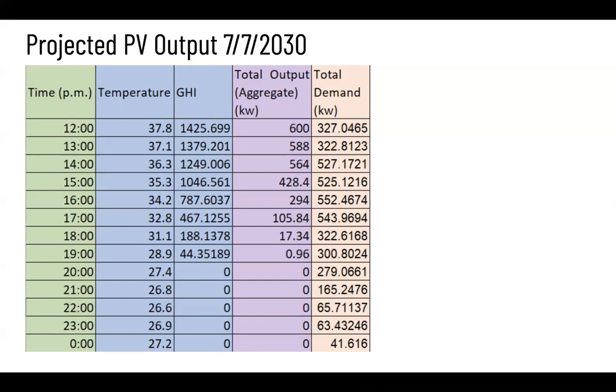So this was a table that we created in order to build our ETAP cases. We decided to use ETAP to run some steady state load flow analysis in order to not only verify the sizing of our PV and battery storage system, but also make sure that there weren't any violations or issues or any upgrades needed to our microgrid system.